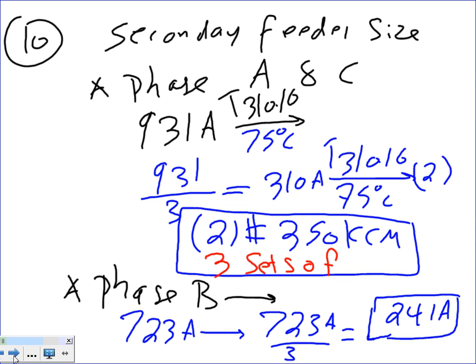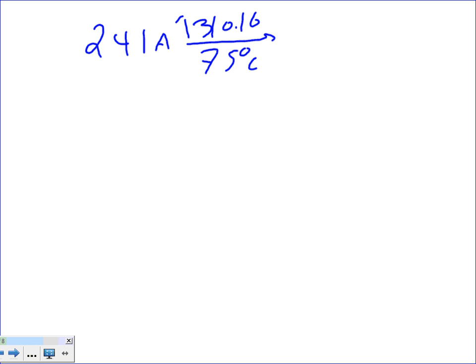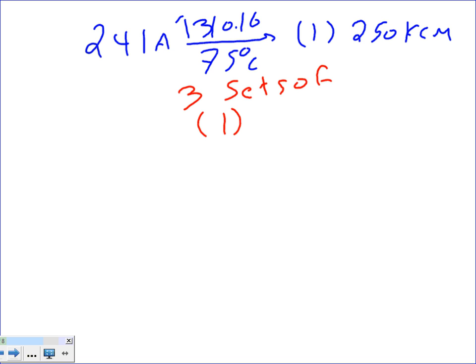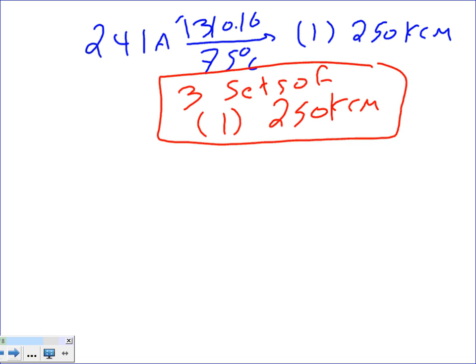Let me draw them in a second here, guys. Just give me 1 second. So if you take the 241 amps, take it to the 310.16 table, 75-degree column, you're going to end up with 250. Did we say 250? 1 conductor, 250 kcmil. So we're going to have 3 sets of 1 conductor, 250 kcmil. Never mind, I just answered my question. 3 sets of 1 conductor for this particular phase.